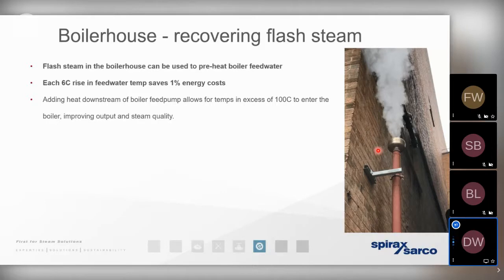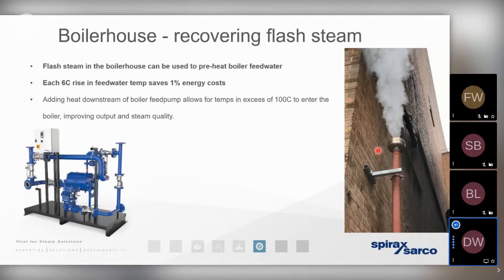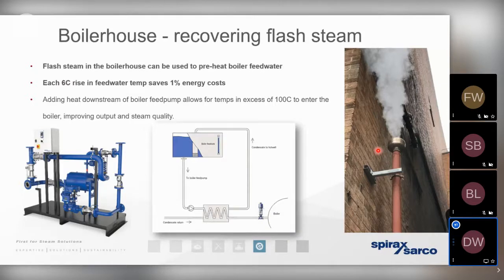Ways that we can recover that flash steam can be something along the lines of a dedicated flash recovery energy management device. And typically that will be used to add energy to another heat sink. For example, we could use it to preheat the boiler feed water, so the water that was leaving the feed tank could take on an excess of energy before it was injected back into the boiler again. The key thing is that we see flash steam as having a value and not simply being a byproduct that we need to expel to atmosphere to protect against that expansion.